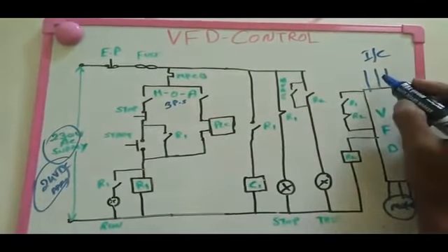At that time we need the indications - if you stop, the stop indication will come on; if you start, the start indication will come on. In case of any fault, the VFD sends the fault signal to the R2 relay. The R2 relay coil energizes and the R2 NO contact closes, so the trip indication will be shown. The trip signal goes to the outside of the panel. The MPCB - motor protection circuit breaker - also gives a supply signal. All the VFD signals for start and stop are used here.